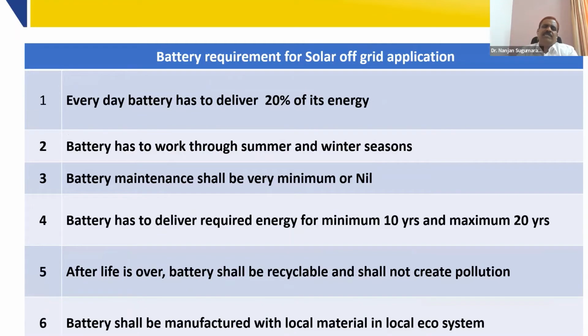Now, what are the requirements in solar off-grid application? In the solar off-grid application, every day, the battery has to deliver 20% of its capacity. Say, for example, if you install a 200 Ah battery for a residential solar, every day the battery should deliver 40 Ah from the battery.